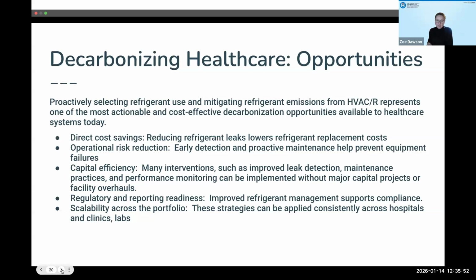So just a few examples. Managing refrigerants can absolutely help create immediate cost savings. If you're preventing refrigerants from leaking, you're lowering refrigerant replacement costs. For any systems operating on phased-out refrigerants like R22, this can be a significant expense, and we've already seen and validated an increase of over 1,000% in the cost of R22 throughout its phase-down and phase-out period.